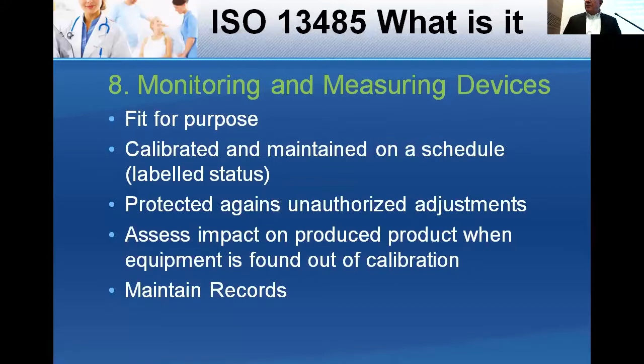Assess the impact on the product when equipment is found to be out of calibration. All product produced using that device when it was found out of calibration needs to be assessed for risk. Then maintain records of the installation qualification, operational qualification, and all calibration and maintenance records, etc.